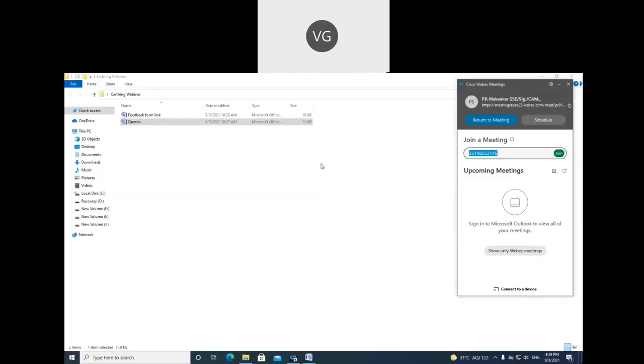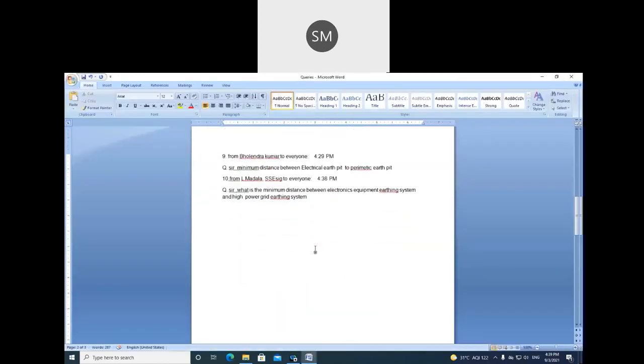Okay, Mr. Stanley, one more question. Suppose my earth is present higher than the ground level, say 10 to 12 meters high. Then how to provide proper earthing in that case? Suppose in hilly areas, it becomes difficult to achieve a very low value of earth resistance. Then what should we do? Is it a rocky area? Rocky area. Okay, so is it possible to dig an earth pit, a vertical earth pit, or can you have a horizontal earth pit where the earth electrodes can be installed horizontally?